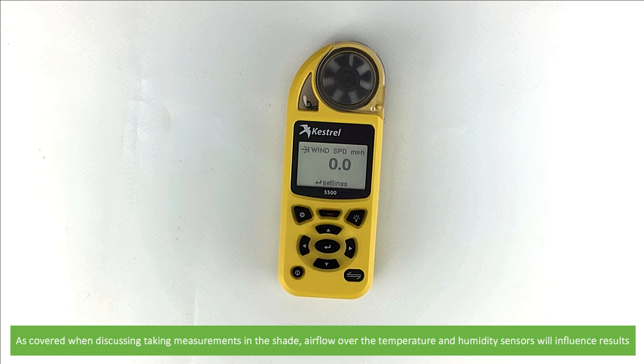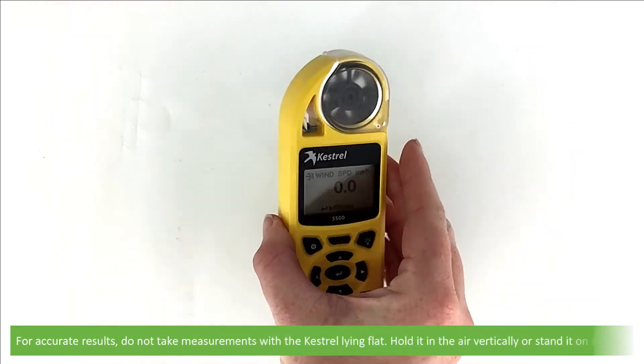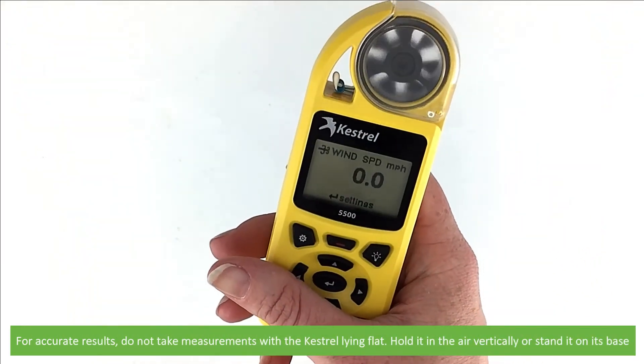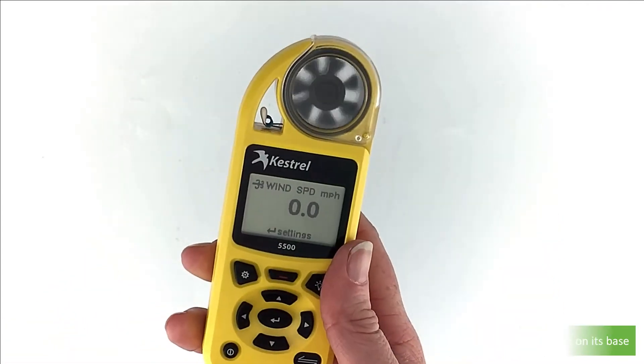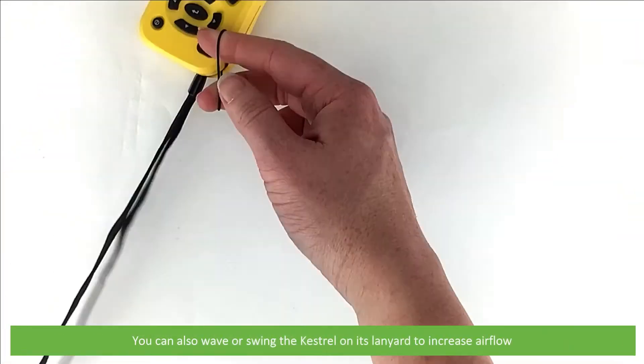Airflow over the temperature and humidity sensors will influence results. For accurate results, do not take measurements with the Kestrel lying flat — hold it in the air vertically or stand it on its base. You can also wave or swing the Kestrel on its lanyard to increase airflow.